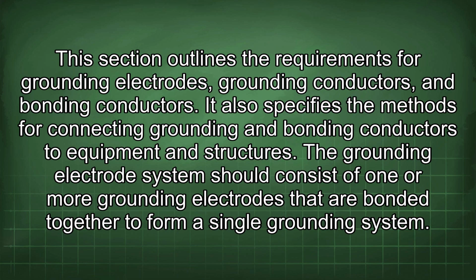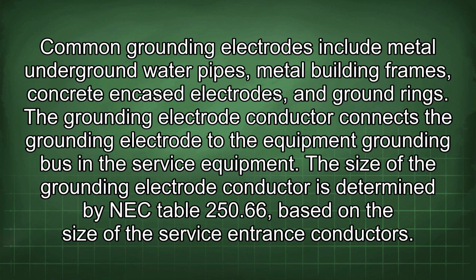The grounding electrode system should consist of one or more grounding electrodes that are bonded together to form a single grounding system. Common grounding electrodes include metal underground water pipes, metal building frames, concrete encased electrodes, and ground rings. The grounding electrode conductor connects the grounding electrode to the equipment grounding bus in the service equipment. The size of the grounding electrode conductor is determined by NEC Table 250.66 based on the size of the service entrance conductors.